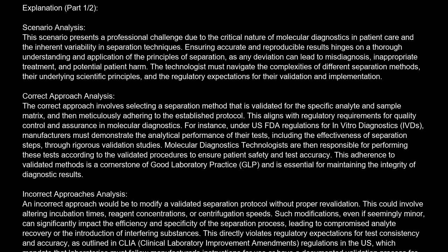The correct approach involves selecting a separation method that is validated for the specific analyte and sample matrix, and then meticulously adhering to the established protocol. This aligns with regulatory requirements for quality control and assurance in molecular diagnostics. For instance, under U.S. FDA regulations for in vitro diagnostics (IVD), manufacturers must demonstrate the analytical performance of their tests, including the effectiveness of separation steps, through rigorous validation studies.